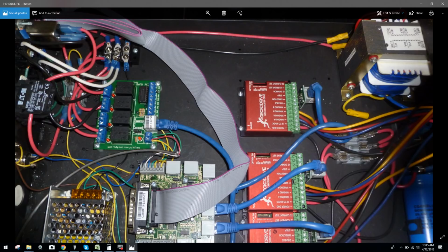Okay? It also tells me that usually crappy engineering is involved because they're not taking the time to look at ways to integrate soldering that would streamline their build process, along with also looking at what this system can do as far as having all your connectors hooked up. Now, you look over here on your input, you can see we have insulated quick connects, which is actually the right thing to do if you're going to use them. They should always be insulated on every terminal. I'll say that again. Every terminal inside your controller should be properly insulated.